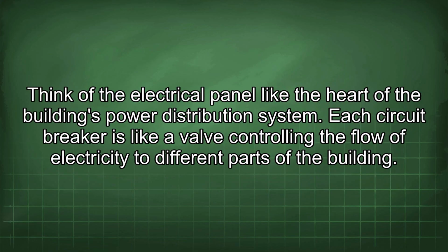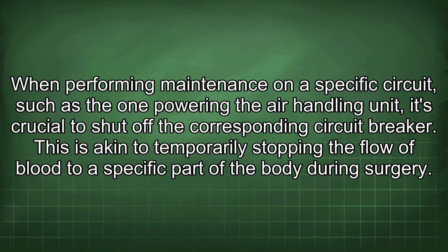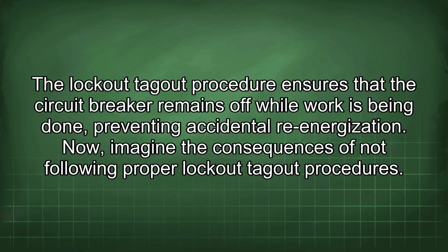Think of the electrical panel like the heart of the building's power distribution system. Each circuit breaker is like a valve controlling the flow of electricity to different parts of the building. When performing maintenance on a specific circuit, such as the one powering the air handling unit, it's crucial to shut off the corresponding circuit breaker. This is akin to temporarily stopping the flow of blood to a specific part of the body during surgery. The lockout tag-out procedure ensures that the circuit breaker remains off while work is being done, preventing accidental re-energization.